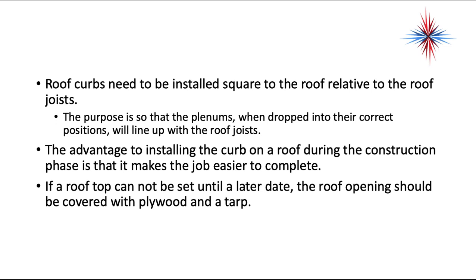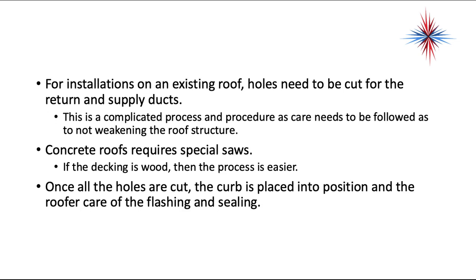Roof curbs need to be installed square to the roof relative to the roof joists. The purpose is so that the plenums, when dropped into the correct positions, will line up with the roof joists. The advantage to installing the curb on the roof during the construction phase is that it makes the job much easier to complete. If a rooftop unit cannot be set until a later date, the roof opening should be covered with plywood and a tarp. For installations on an existing roof, holes need to be cut for the return and supply duct.